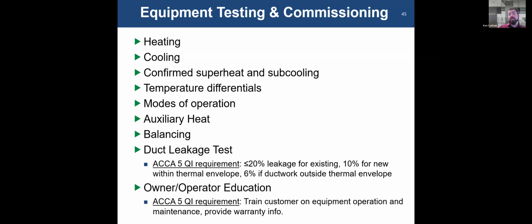It tells you in a heat pump operation, right, that your auxiliary heat or your secondary stage of heat is only working at the point at which your heat pump can no longer maintain the load, right? So that you're not using your auxiliary heat with your heat pump at all times. That would be energy inefficient. You want to use the heat pump first and then your auxiliary heat. It does discuss balancing of systems. We'll talk a little bit about that next.